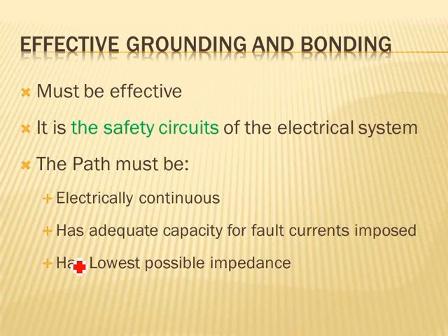So what happens if you forgot, which happens in stories, or people forget? Now you worked on it, de-energized it, put it in a safe working condition, and you came back to energize the system. You forgot that you put this bonding jumper on. And it did happen, believe me, it did happen. I know of a scenario where it happened and someone flipped the switch. Now you've got yourself a phase-to-phase-to-phase short circuit. That's the scenario you would have.